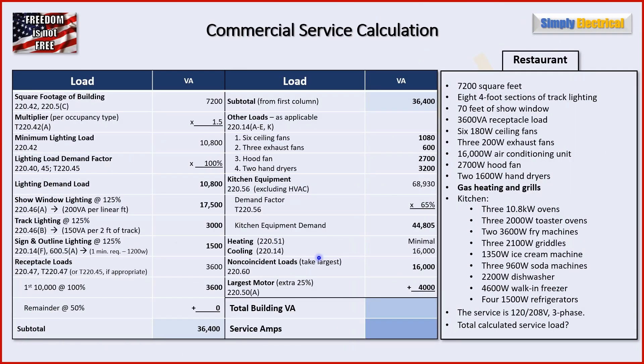Now we compute our heating. We have gas heating, so there's minimal electrical heating load — just the fan motor to circulate the heated air, which we don't know precisely, so we put it as negligible. Under 220.60, for non-coincident loads, we take the largest of the two loads that don't operate at the same time. Since our heating is all gas, the cooling will be a much larger load — so we take the 16,000 VA for cooling and ignore the heating.